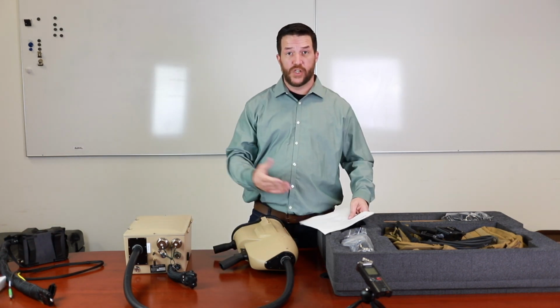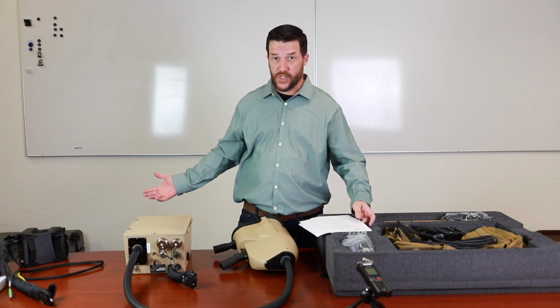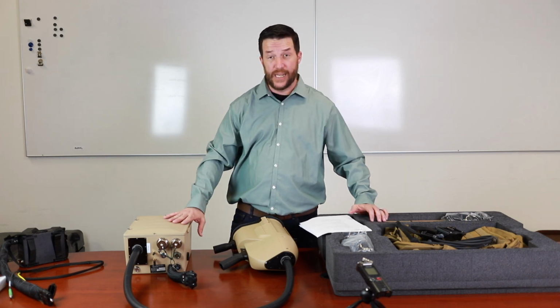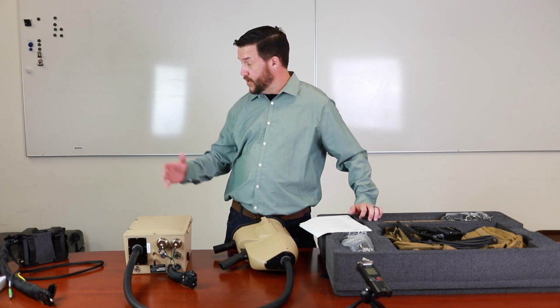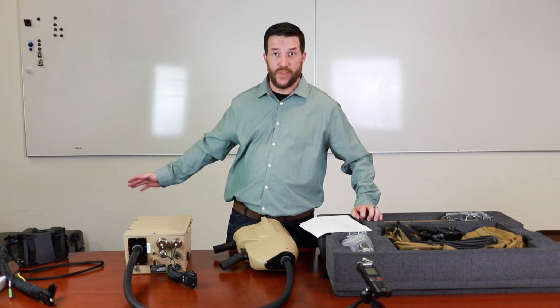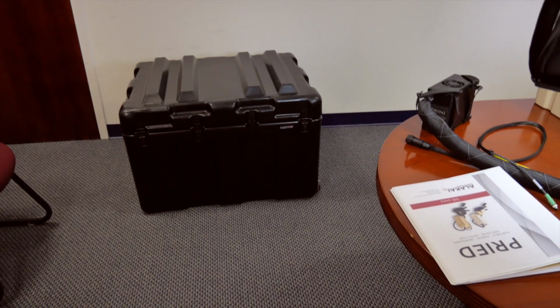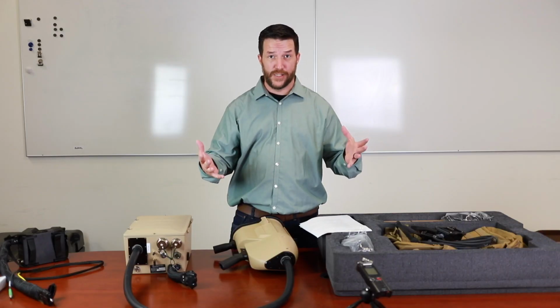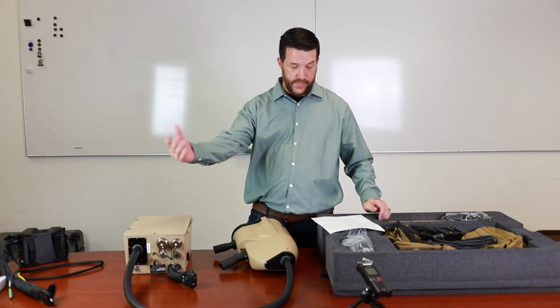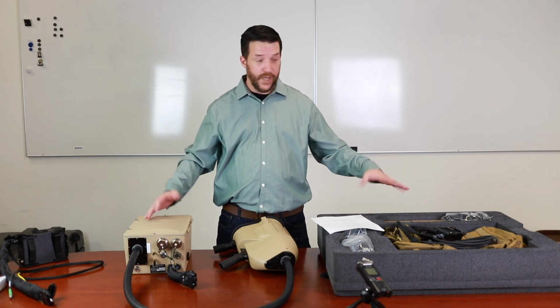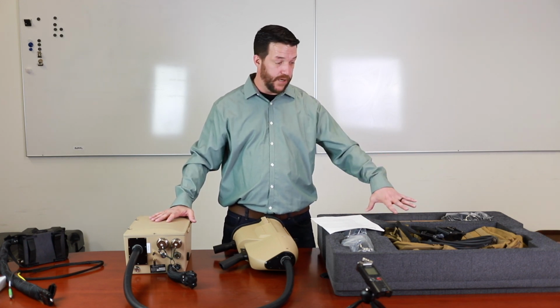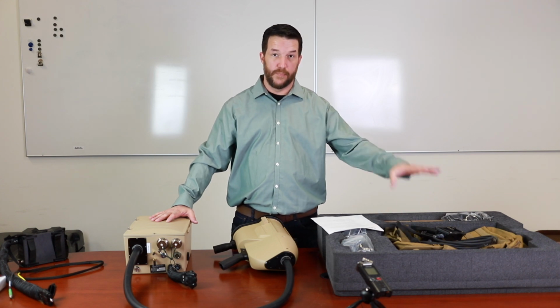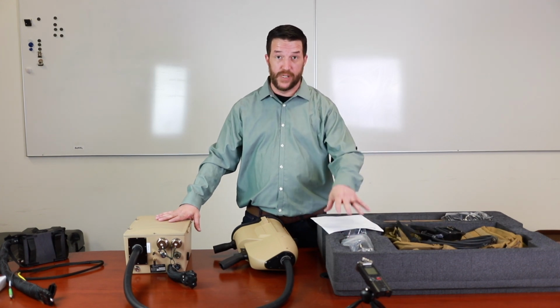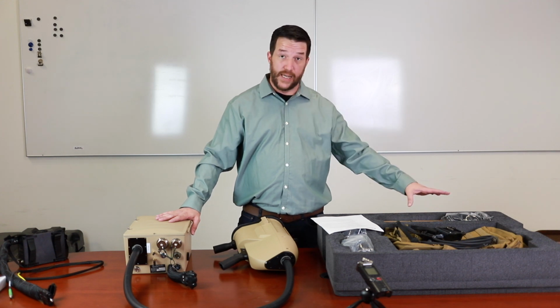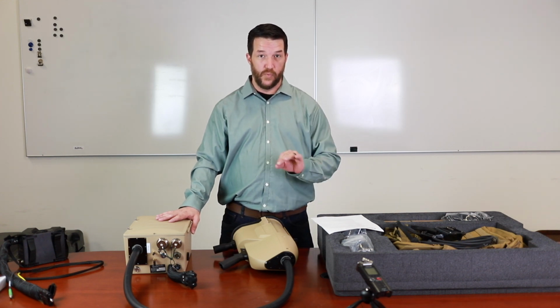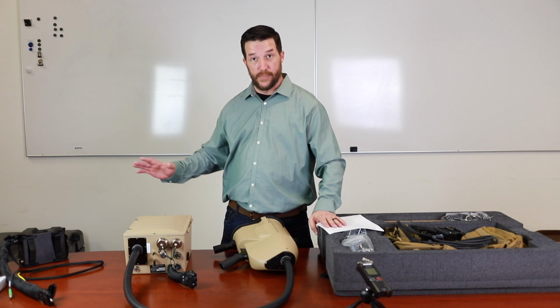First thing, we want to check and make sure there's no excessive damage to our shipping cases or anything like that. It might indicate more damage on the inside. So if there's any excessive damage, take note of that, take pictures, and document what we have on our shipping case. It should be very nicely brought to you. Step 2 is going to be unpacking, which is what we did. Brought the top piece of our case out, which is going to have our backpack, our battery cables, batteries, fill kit, and the accessories kit. So everything you'll need to go operational with your system is in the main black shipping case.